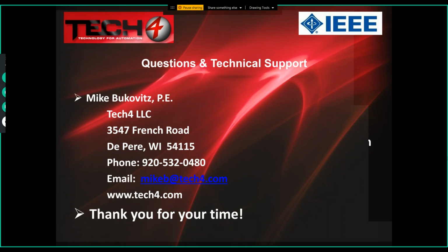John Levine noted the GE Multilin T35, 845, T60 are all transformer differential protection that they offer. Donald Ray said personal protection is more important than coordination: jumper the arc flash switch input always on, remove the chance that someone doesn't actuate the switch when they should, and coordinate using the faster trip time. That's an option, and again, I fully acknowledge that's allowed by the National Electric Code, one of the approved methods of 240.87 mitigation.